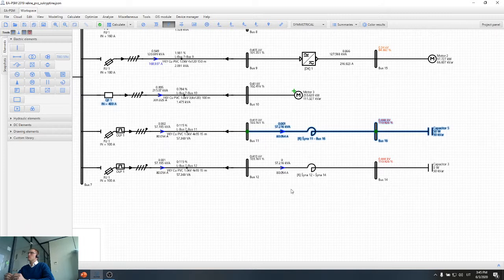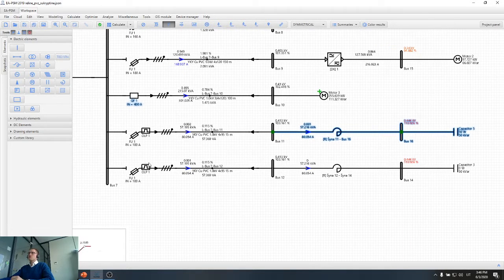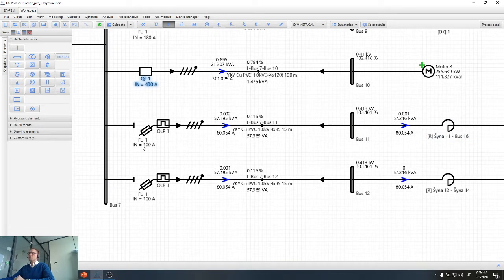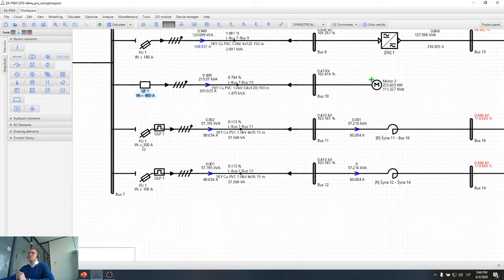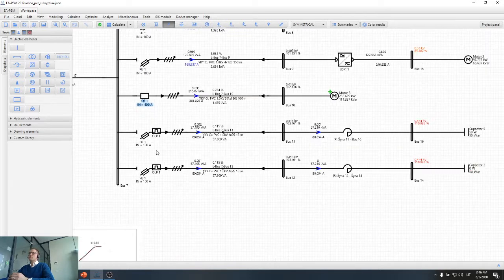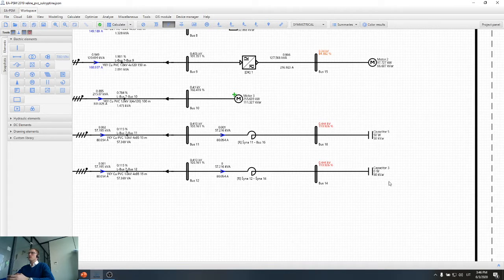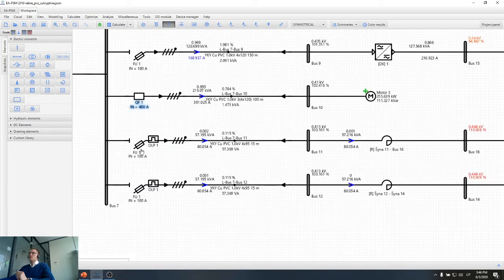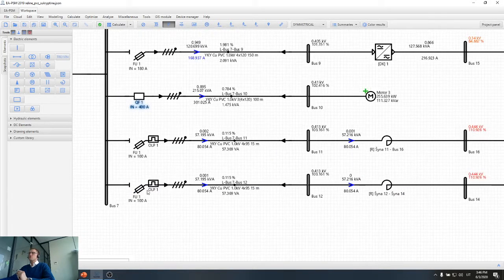However, we also need to protect our capacitor bank from the short circuit. For short circuit protection, we can use fuses as one of the cheapest protection types. What we need to make sure is that each step of the capacitor has a separate fuse. So it's not possible to put only one fuse for, let's say, the whole power bank. You can see that I have two steps here. Here's my power bank of two capacitors, and each of the capacitors has separate fuses. This is very important to ensure protection of each capacitor, because normally if only one capacitor is affected by the short circuit, the current won't be big enough for the fuse to disconnect if you select a very powerful fuse.